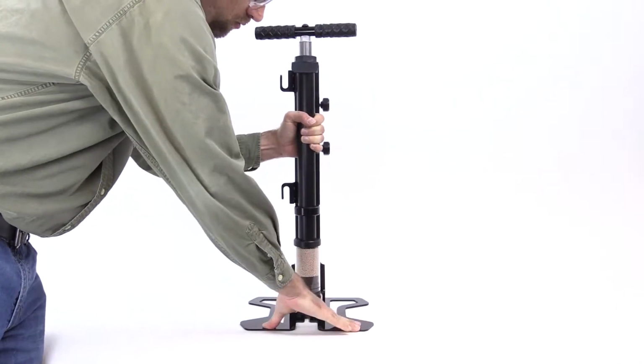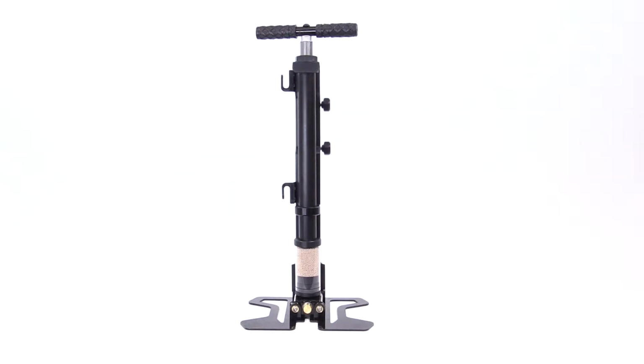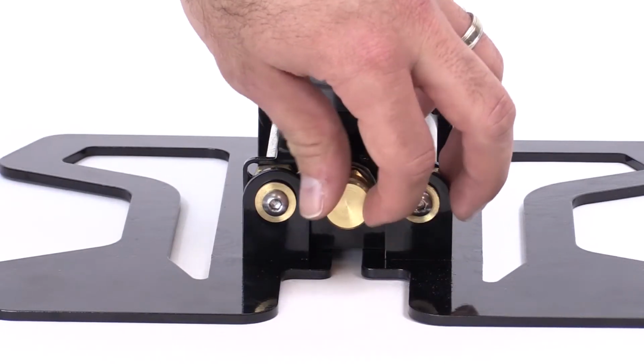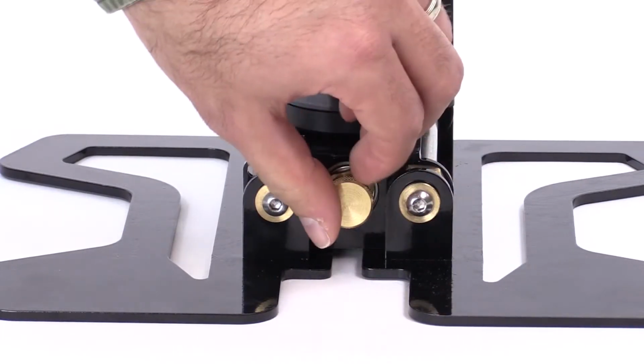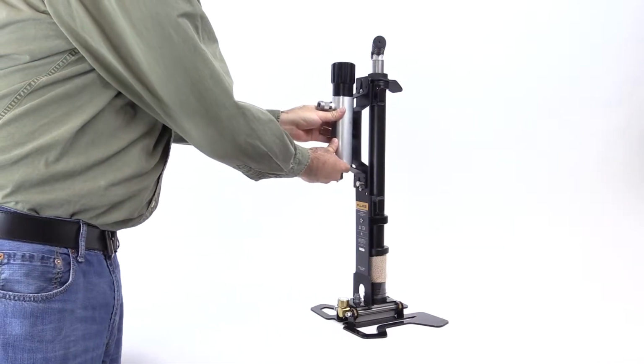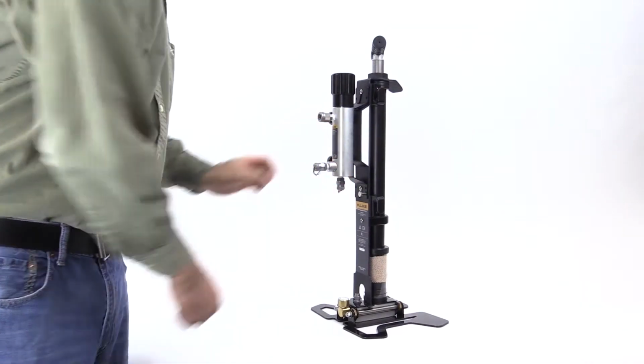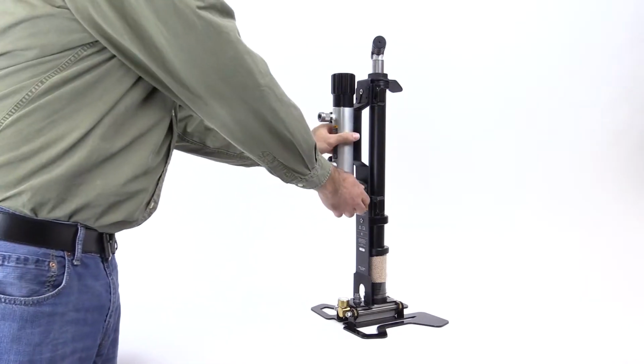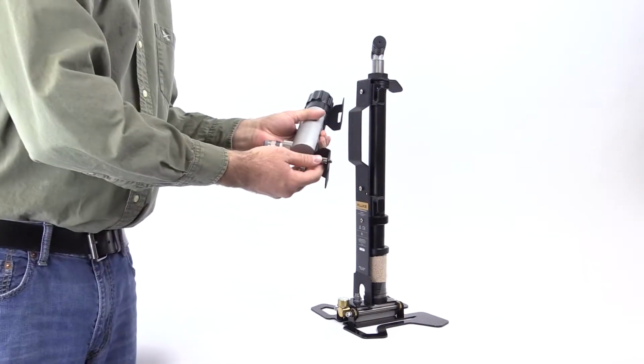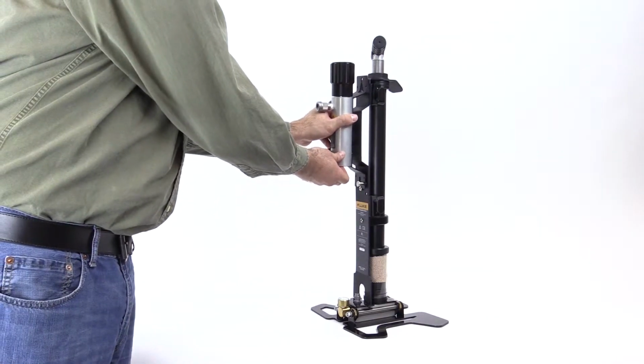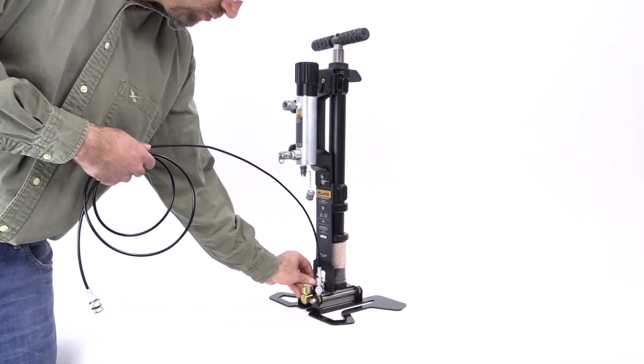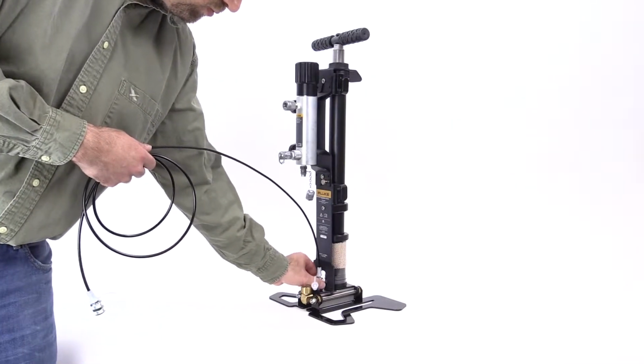Place it on almost any surface and open the legs to stabilize it. Make sure the vent valve at the bottom of the pump is completely closed. Connect the calibration manifold to the pump bracket. Quick detent pins make the manifold easy to connect and disconnect. Connect one end of the first hose to the port at the base of the pump.